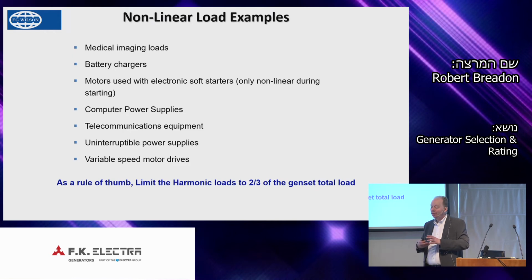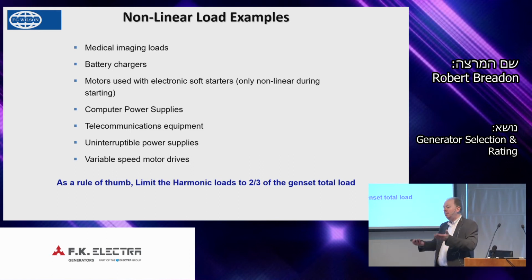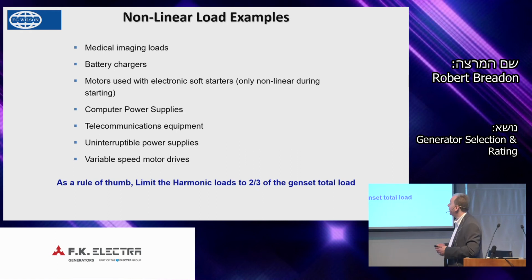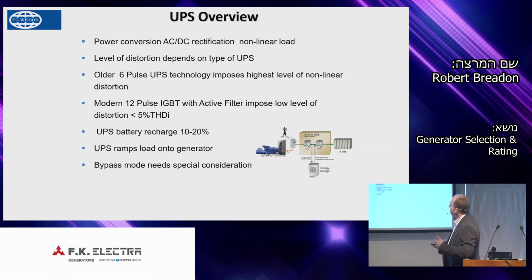We're putting a larger alternator on the machines, a high voltage machine. So that's the sort of impact this can have if it's not considered, and that's why in complex applications, the applications team in Larne, we like to consider them, because you can end up in a very difficult situation where you have enough kilowatts to drive your load, but your alternator's burning out or you're damaging other equipment. So we can help with that. We have a team that can help with that selection if you have more complicated projects.